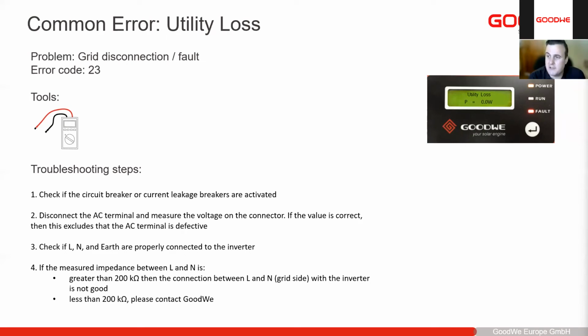We can also make sure that the voltage is correct. Check the live, neutral, and earth on the inverter. Measure the impedance between live and neutral on the inverter itself. So if it's greater than 200 kilo ohms, then the inverter is good. If it's less than 200 kilo ohms, then there's a problem with the inverter, and you need to contact us.